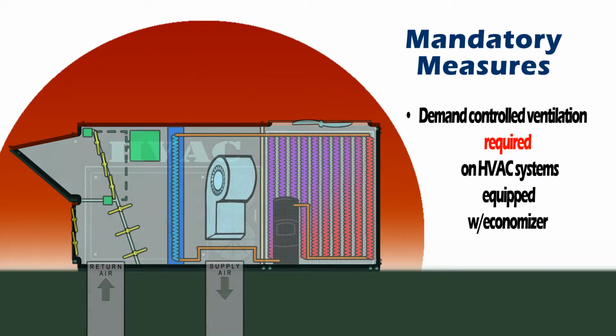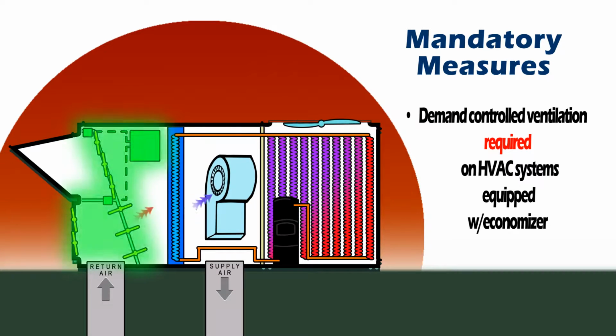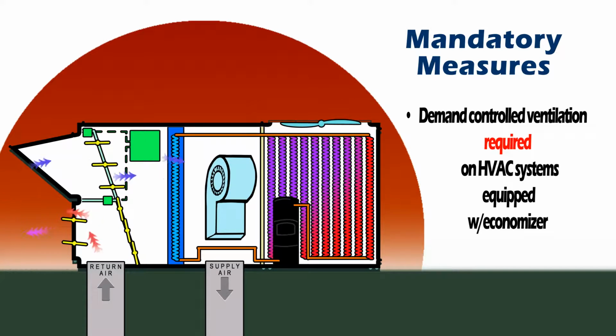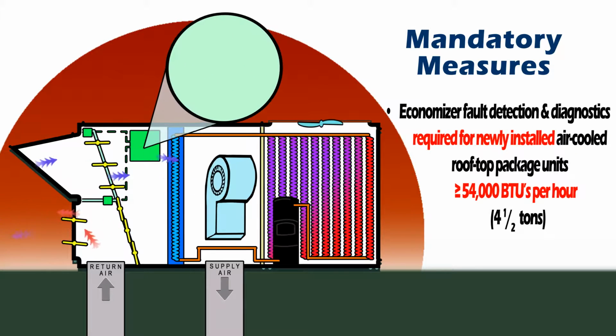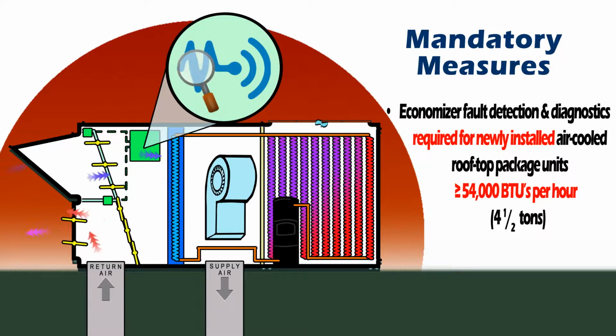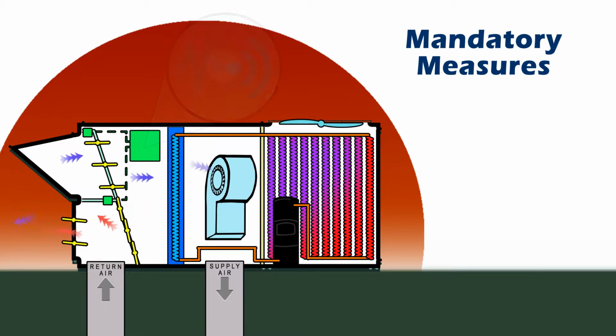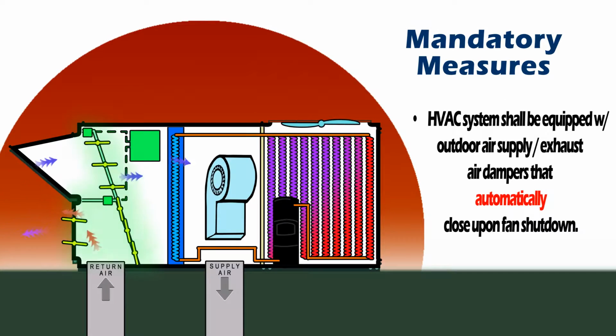Demand-controlled ventilation is required on HVAC systems that are equipped with an Economizer, which is a system of controls and dampers that utilizes outdoor air to provide free cooling when the outdoor conditions are suitable. Economizer fault detection and diagnostics is required for all newly installed air-cooled rooftop package units equipped with an Economizer and with a mechanical cooling capacity greater than or equal to 54,000 BTUs per hour, or approximately 4.5 tons. Each HVAC system shall be equipped with an outdoor supply damper and exhaust air damper that shall automatically close upon fan shutdown.